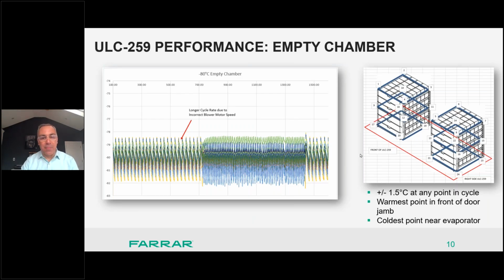Our empty chamber performance at minus 80 C is plus or minus 1.5 degrees at any point in the freezer. With a max temperature of minus 78.5 and a min temperature of minus 82, it's well within the tolerance of a customer's uniformity requirements. The tighter spacing between that sawtooth in the middle of the graph was for our engineers optimizing the blower motor speed to see if that really mattered. And as you can see, uniformity doesn't change that much in terms of max and min. It just gets a lot closer and tighter between temperature swings between those 4 degrees.